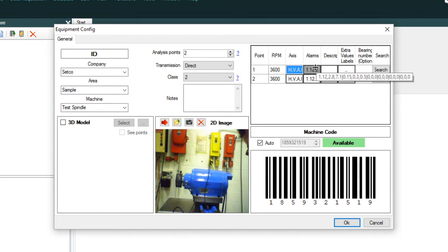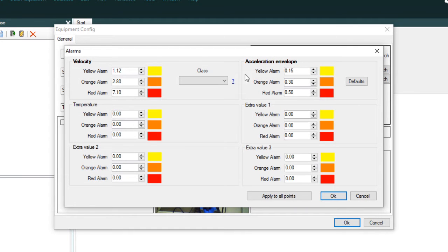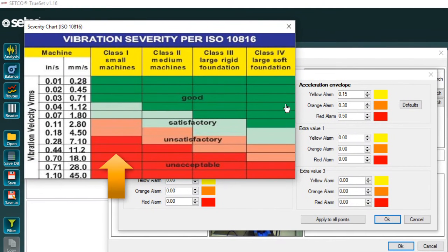The reference axes is used for 3D ODS simulation. For this example, the alarms are set to Class 2, which sets the parameters for the analysis of the equipment. Class 1 would be small items like gyroscopes. Class 3 is larger items like pumps or gearboxes. Setco uses Class 2 for doing analysis on precision spindles.